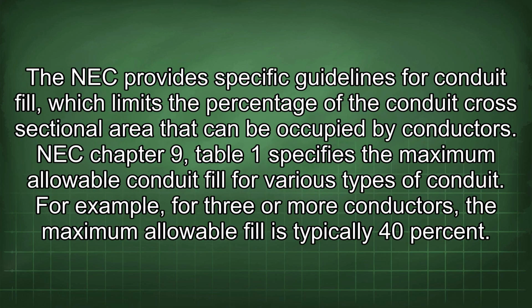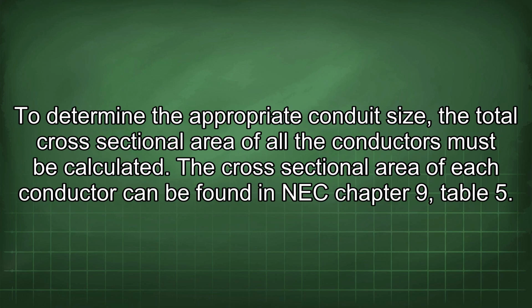The NEC provides specific guidelines for conduit fill, which limits the percentage of the conduit cross-sectional area that can be occupied by conductors. NEC Chapter 9, Table 1 specifies the maximum allowable conduit fill for various types of conduit. For example, for 3 or more conductors, the maximum allowable fill is typically 40%. To determine the appropriate conduit size, the total cross-sectional area of all the conductors must be calculated.